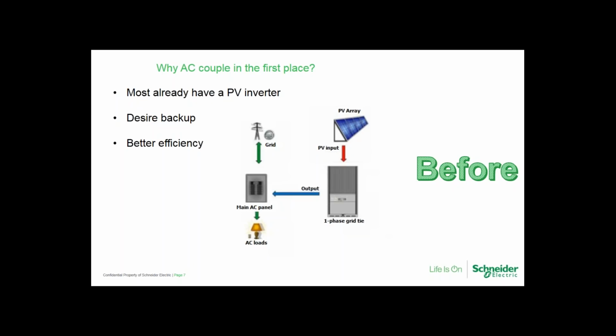So for example, a customer already has a grid tie inverter with PV, and either they're interested in battery backup, or maybe their grid tie inverter has failed out of warranty and they are interested in battery backup. So there are options here. They could go with an AC coupled system, or they could go with DC coupling with our high voltage controller. Both are options, but which one would be better?